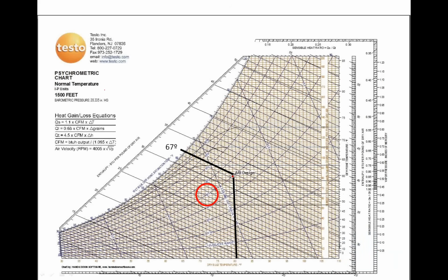So if we're going to take, this is a psychrometric chart, and a psychrometric chart is simply relationships of air. Psychro is the study of air. So what we're looking at here with the center circle is we're at a 50% relative humidity line, and these curved lines going up here, these are relative humidity. So that curved line, if we follow that up, crosses this point here, and it goes right through that red dot on my screen. And then if we plot the corresponding wet bulb temperature, which is right here, this is 65, 66, 67, and here's what I want to show you is that 50% relative humidity at 80 degrees dry bulb, which is down here at the bottom, that corresponds to a 67-degree wet bulb temperature. All right? So the ARI design, when we talk about, because when we look at a charging chart here in a minute, it's not going to give us relative humidity, it's going to give us wet bulb.